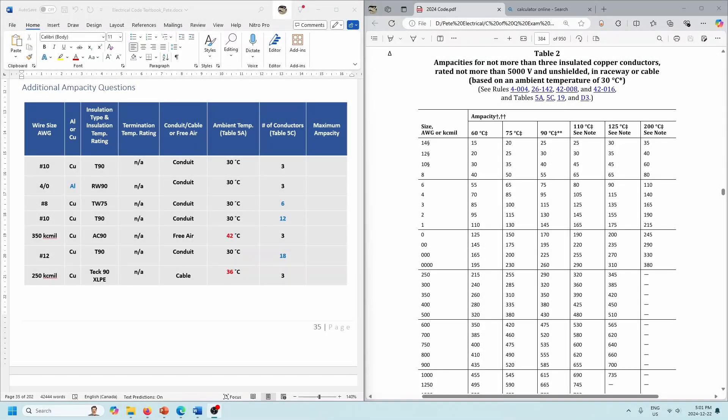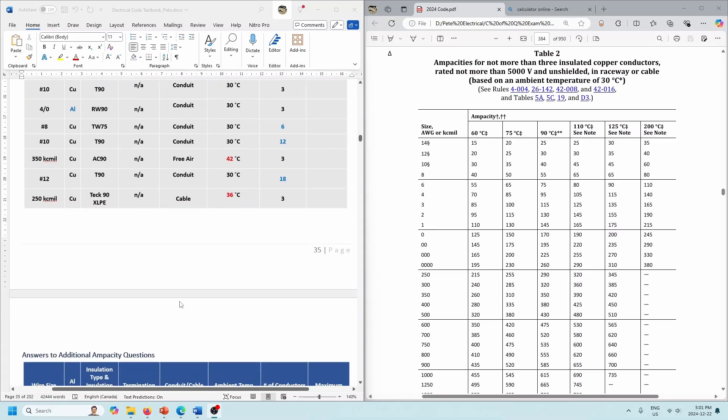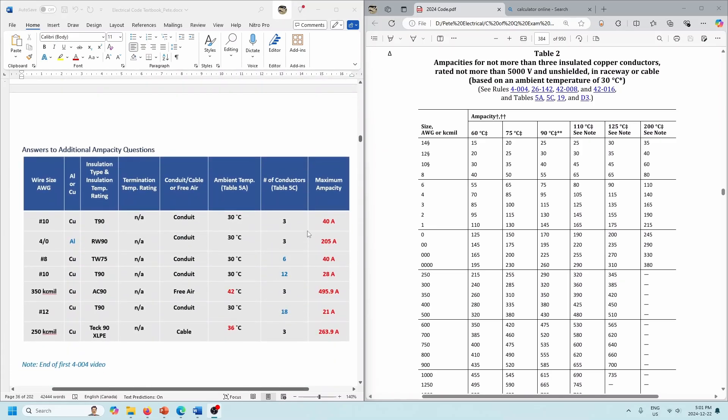Let's go on with a couple of additional ampacity questions. Keep in mind that on the previous video, right at the end, I had a chart with additional questions — there's a mistake there. The 4-aught aluminum was incorrect. So this was the chart that was given, and these are the answers. The answer was 205 amps here. The other question that came up was the 350 kcmil — careful with that one because it's not a conduit installation, it's a free-air installation.